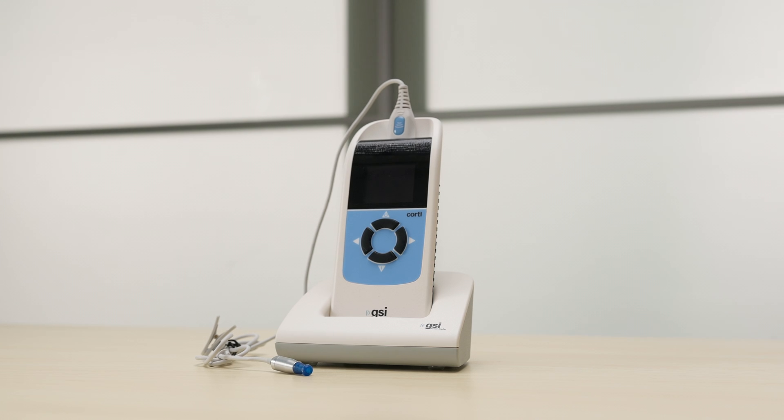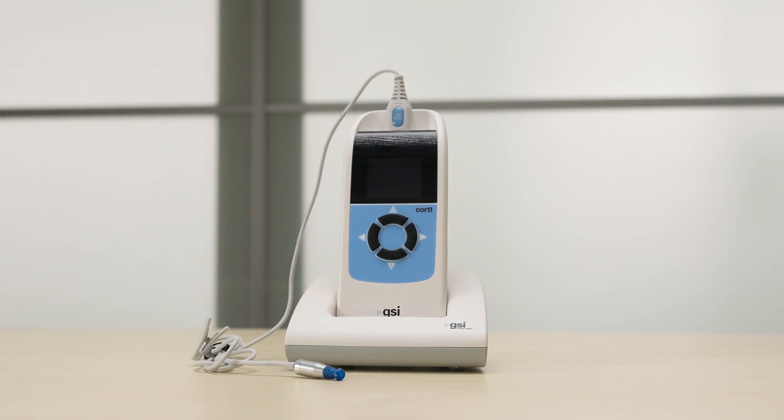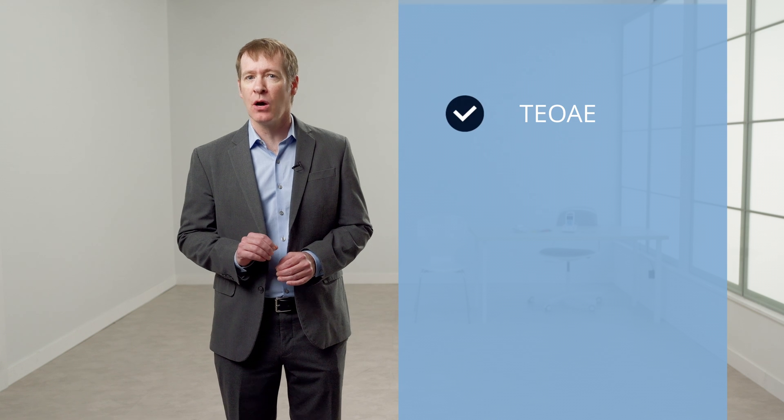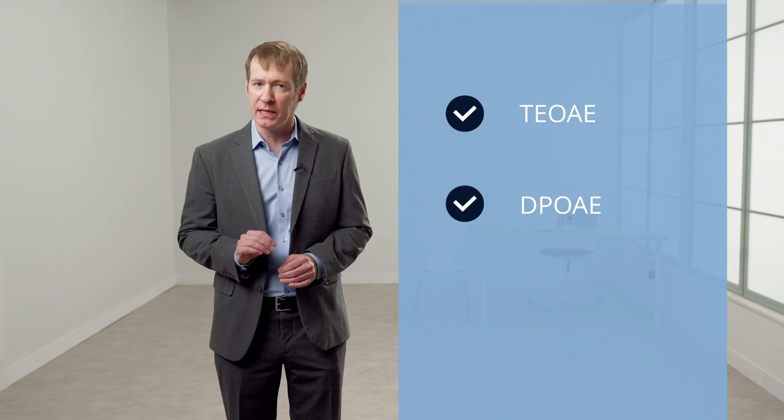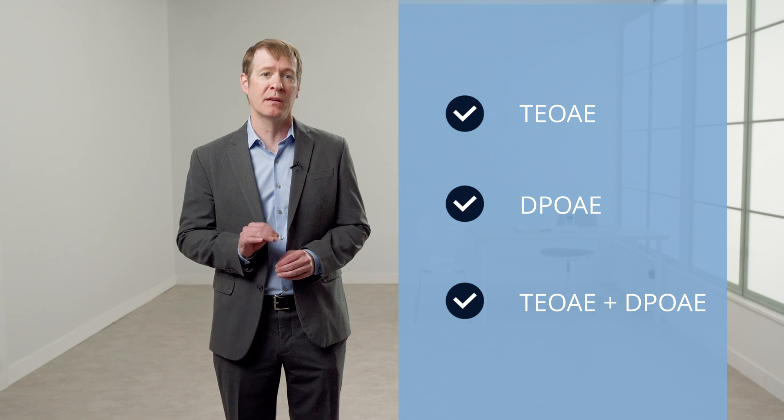Thank you for taking time to watch the GSI Corti tutorial. The Corti is a handheld screening or diagnostic otoacoustic emission device. It features an easy four-button navigation panel and intuitive software in a compact hardware design. The Corti may be configured with TE-OAE, DP-OAE, or both for either screening or diagnostic otoacoustic emissions, making it a great choice for many applications from newborn hearing screening to adult diagnostics.